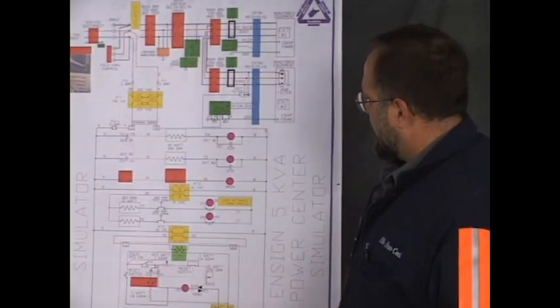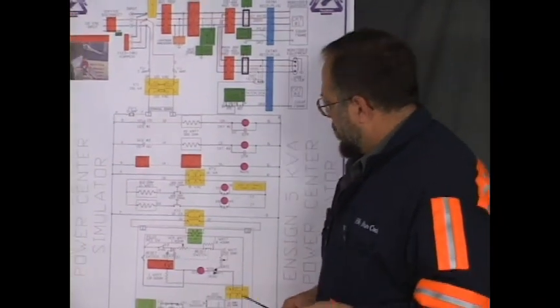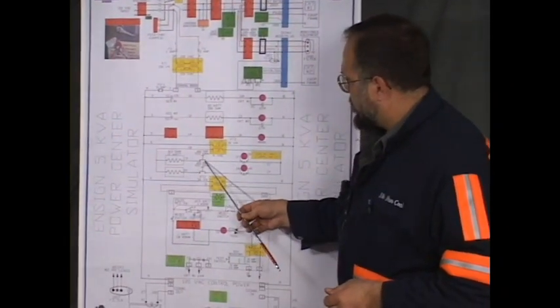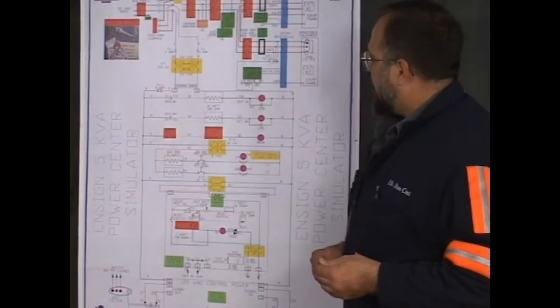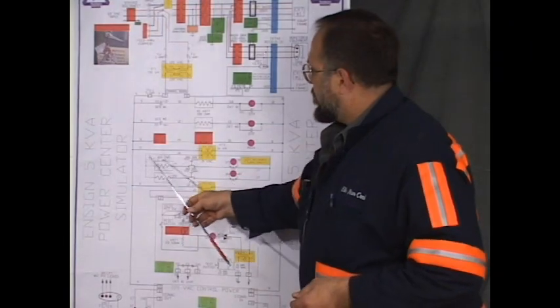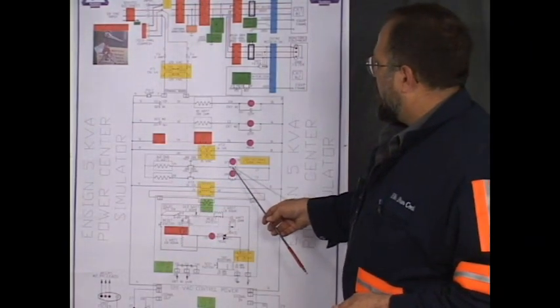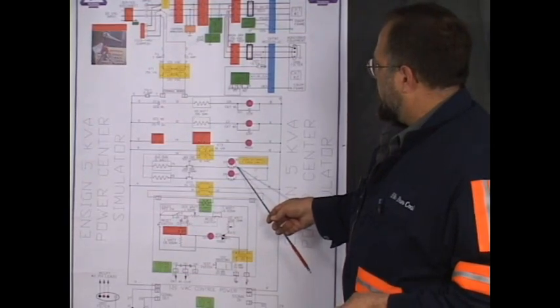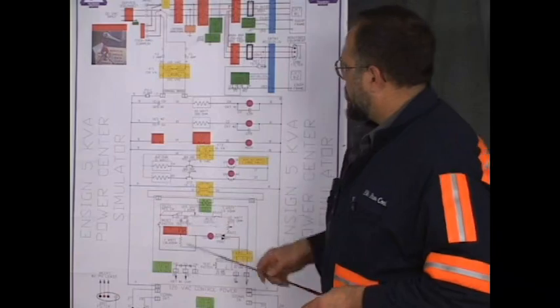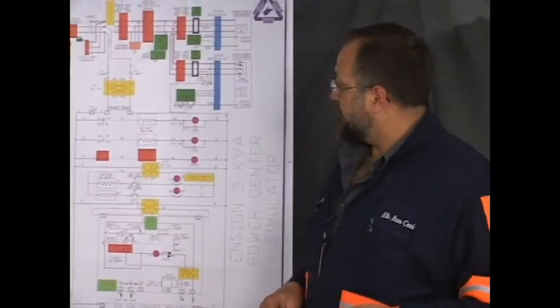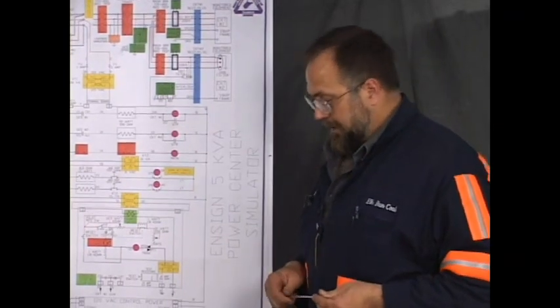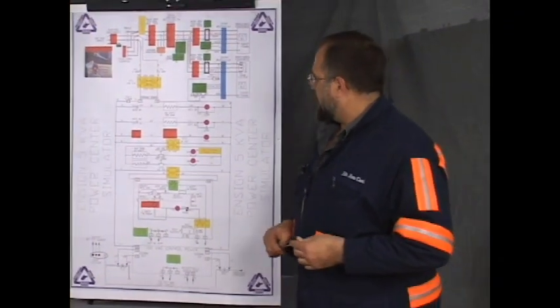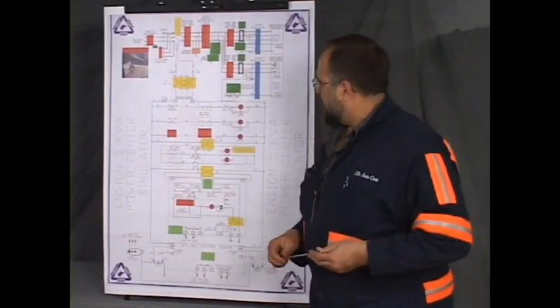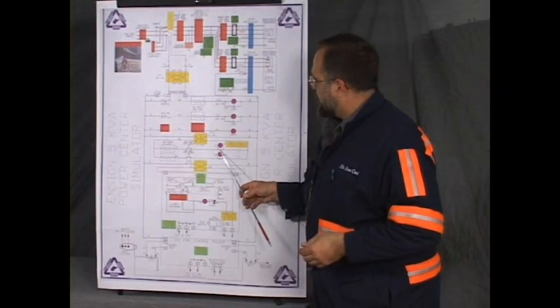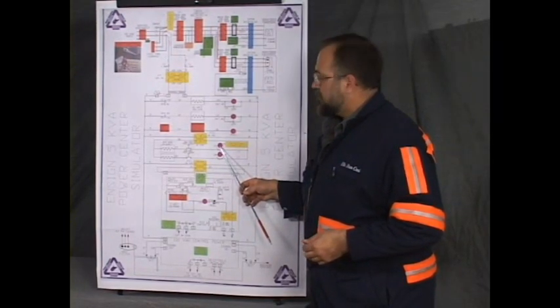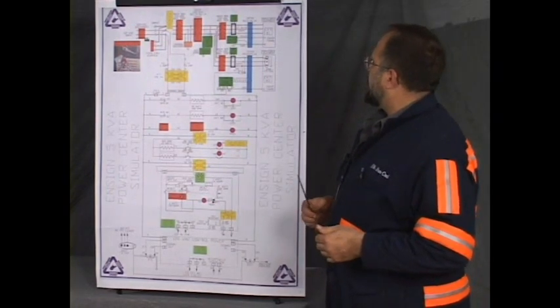But our test circuit isn't operating. When we depress the test switch, ground trip test switch for circuit number 1, what should happen is a current should flow on this circuit through the switch on a wire that passes through the ground trip CT and then back to the transformer. It should make that loop. When it does that, the CT detects current flowing on wire 17, and it in turn induces a current in the CT that powers the GTR relay. This GTR relay, that's the ground trip relay.